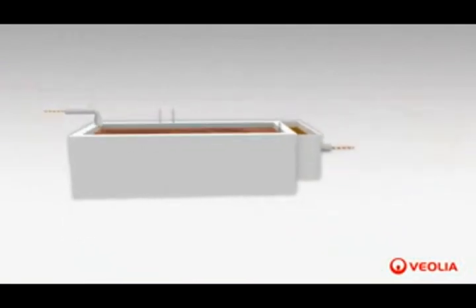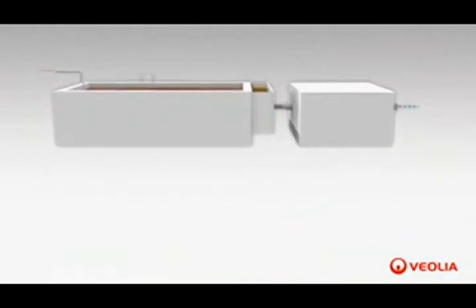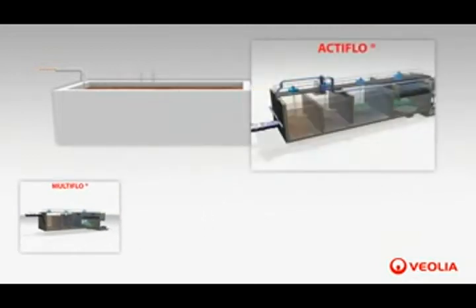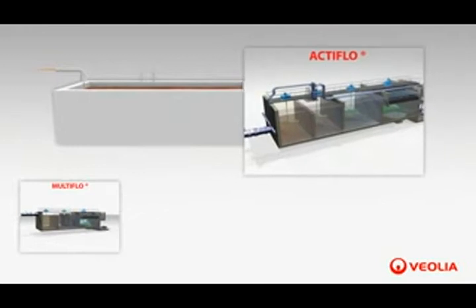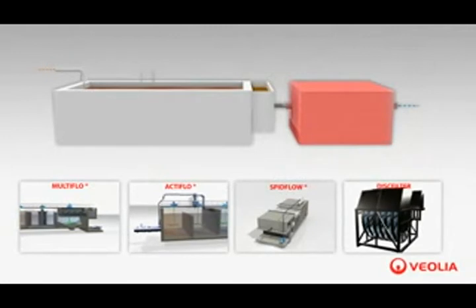Downstream separation is necessary in order to retain the excess sludge before the treated water is discharged into the environment. Multiflo lamella settlers, Actiflo high-speed ballasted clarifiers, and Spidflow rapid dissolved air flotation are often used for that purpose. Another possibility is to replace the settlers with Hydrotech disc filters, which results in a very compact unit.